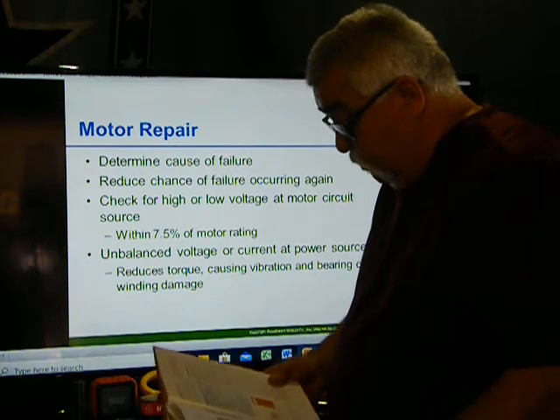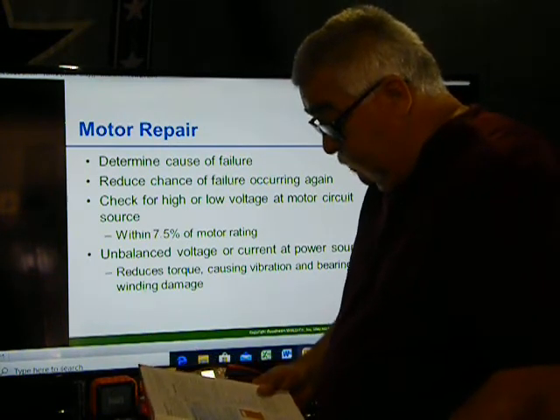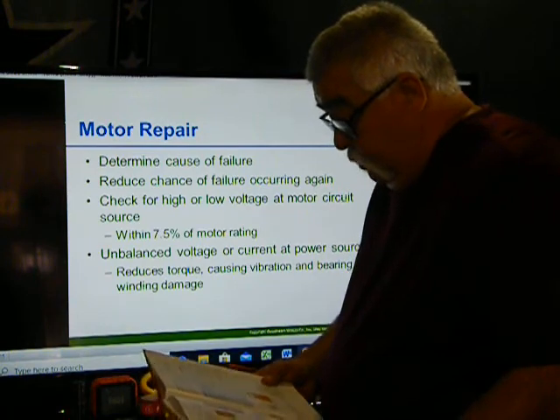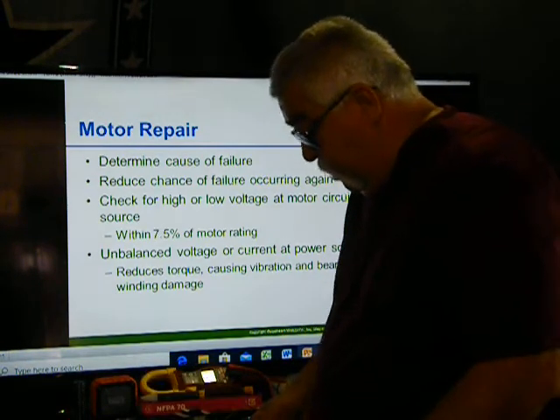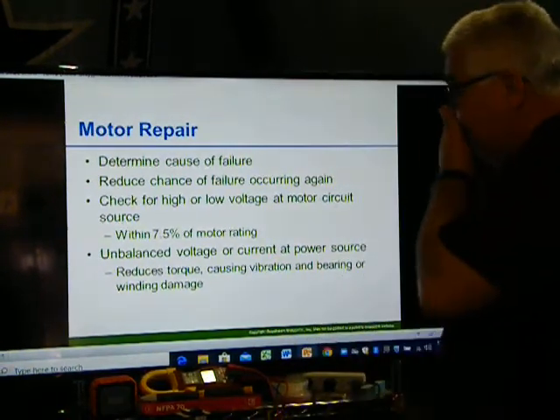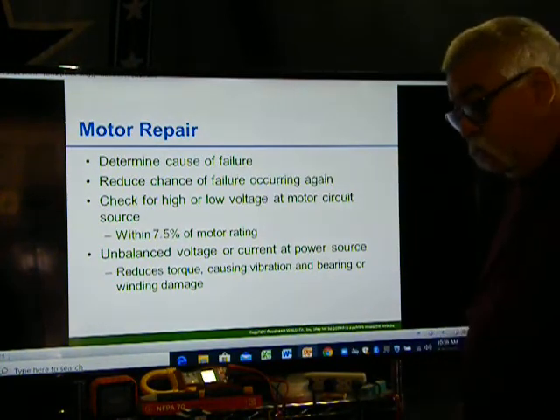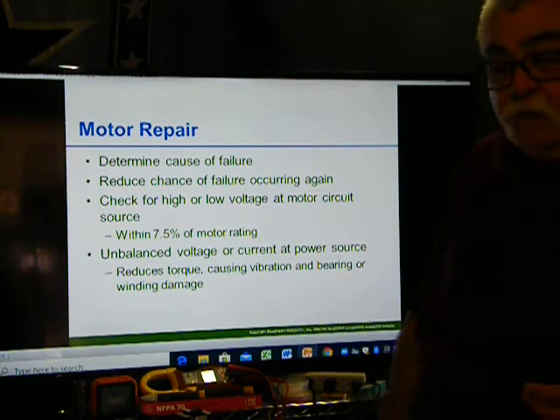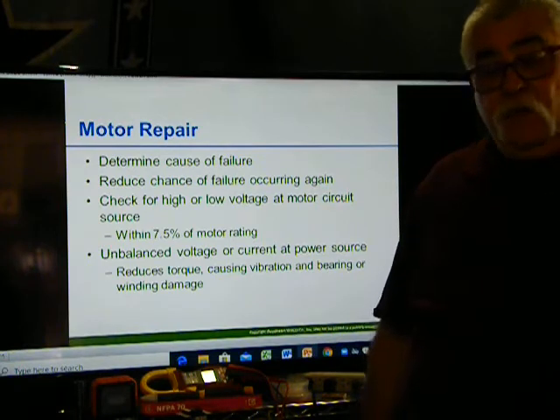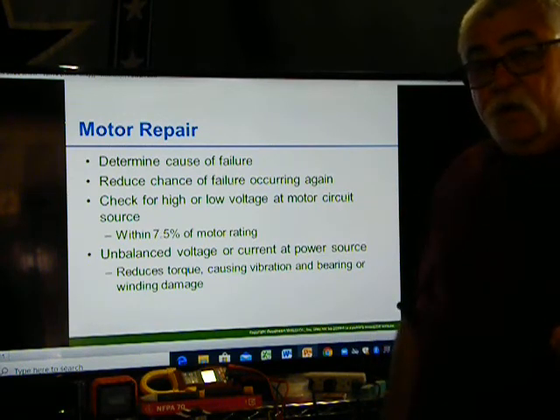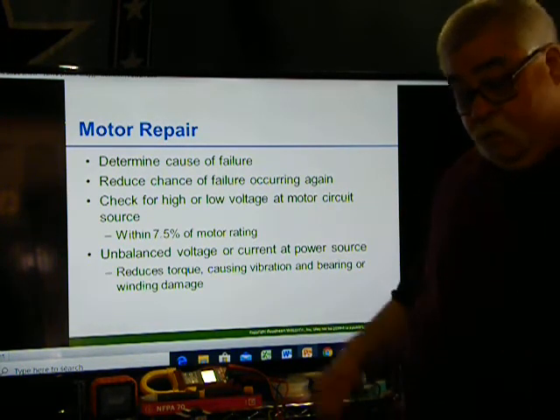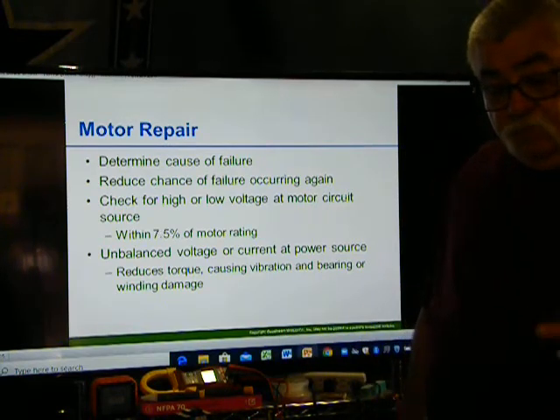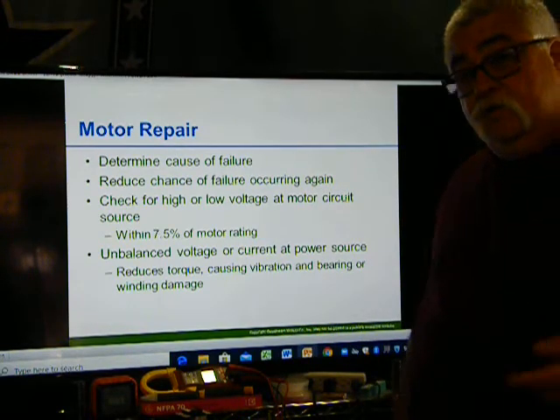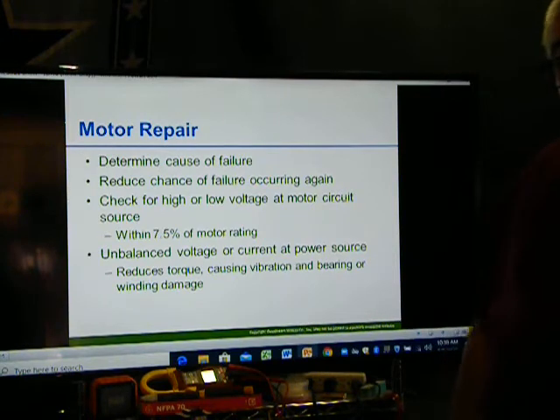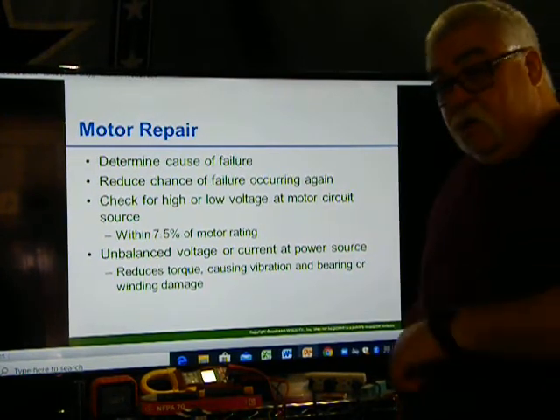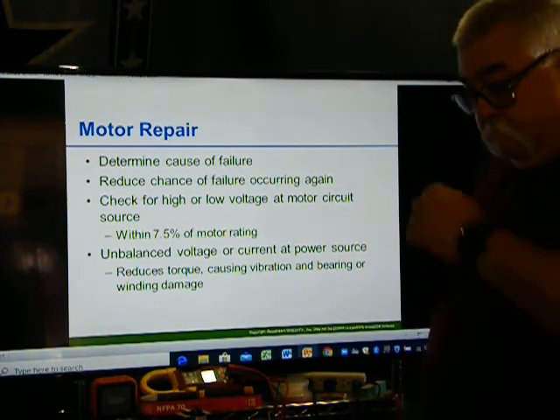Troubleshooting motors involves two basic operation concepts: determine the cause of failure, and reduce the chance of failure occurring again. Okay, so determine the cause of failure. What causes a motor to fail? Okay, so you got an area that all of a sudden started getting hot, or somebody forgot to oil the bearings on it, so it starts to work harder. Okay, that can cause a motor to fail. Why? Because if it has to work harder, it's going to get hotter and then fail.